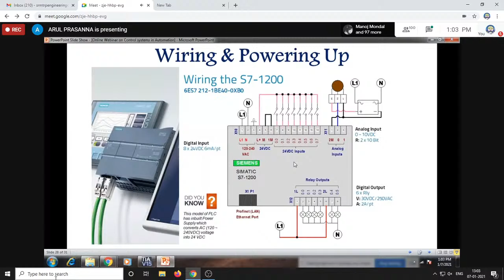Any analog processing can be monitored or controlled through our analog channel via sensor outputs. The sensor outputs might be of two or three types: voltage output or current output. Voltage output sensor means we have to set your analog input channel with voltage calibration. If you have an analog sensor with current output, you have to select a PLC with a current input analog channel. Only then will the PLC be able to process it, if the sensed value is in an understandable form for that PLC.